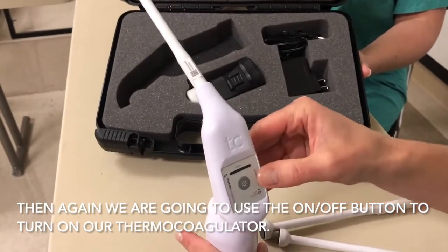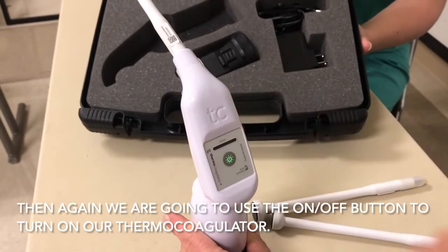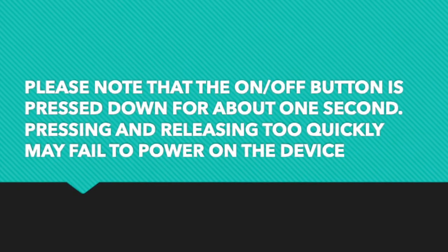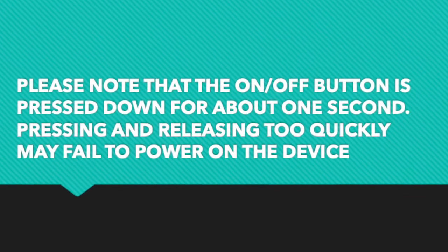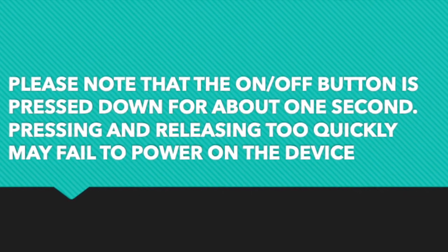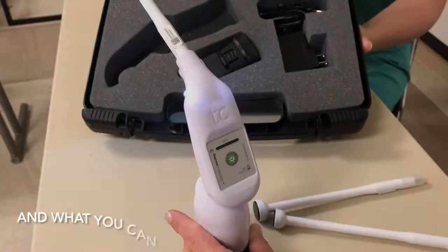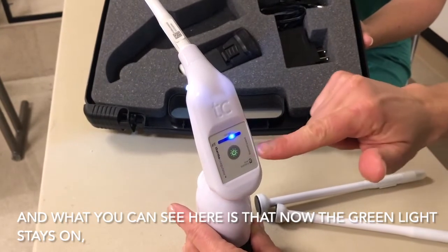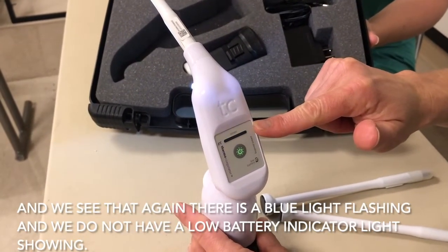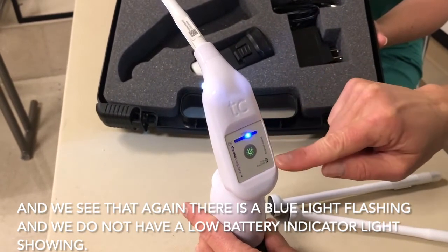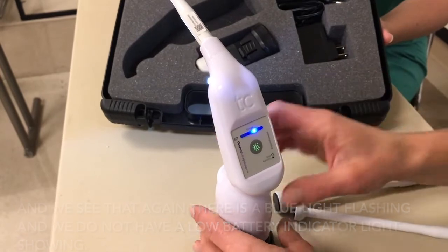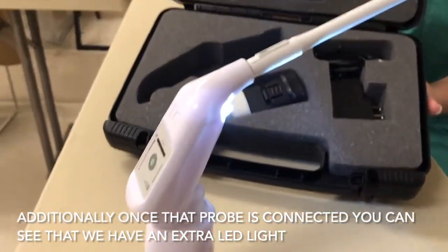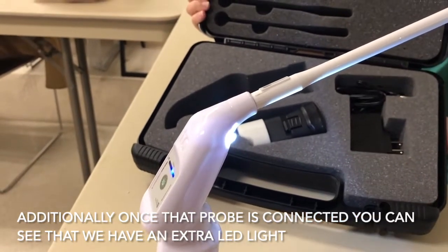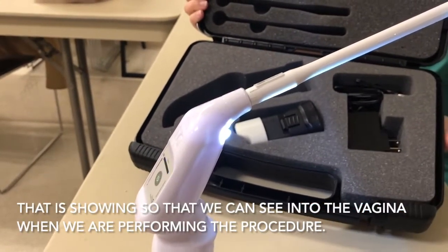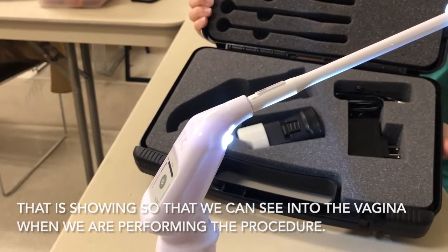Then, again, we're going to use the on-off button to turn on our thermocoagulator. When you want to use the thermocoagulator for a procedure, you press the on-off button for about 1 second. Pressing and releasing too quickly may fail to power on the device. And what you can see here is that now the green light stays on, and we again have the LED blue light flashing, and we do not have a low battery indicator light showing. Additionally, once that probe is connected, you can see that we have an extra LED light that is showing so that we can see into the vagina when we're performing the procedure.